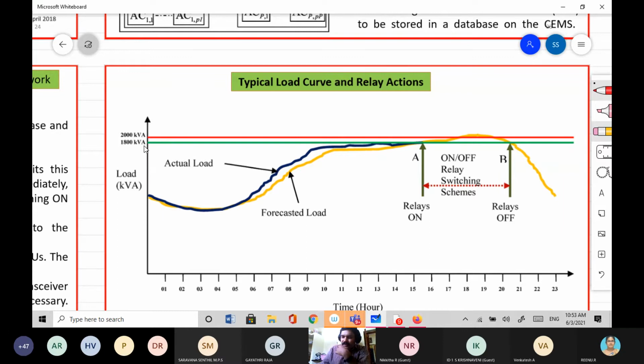We always say there's no smoke without fire, so before it actually crosses the limit, we want to know whether it will cross or not. We take 90% of the load as a threshold, and once it crosses, we switch on the relays. Relay scheduling is done so that, based on priority, we switch the ACs on and off without continuously penalizing the same air conditioning units. We look at all the units together instead of penalizing just one.